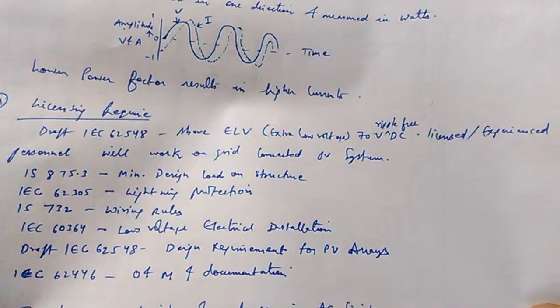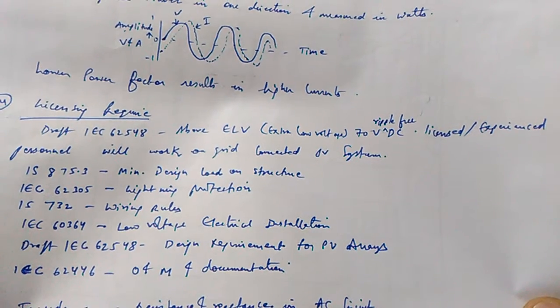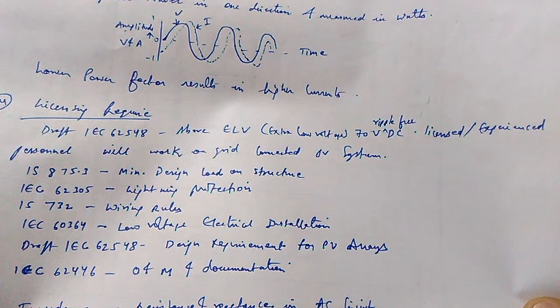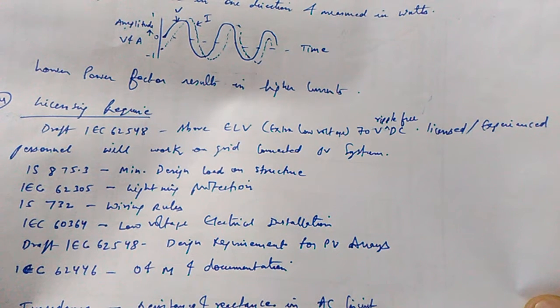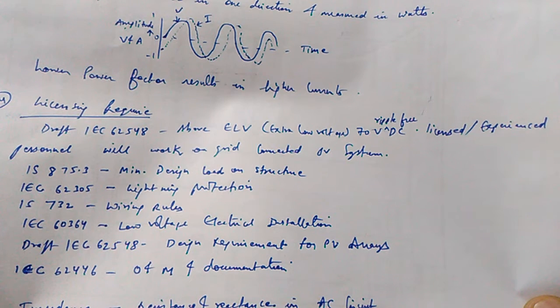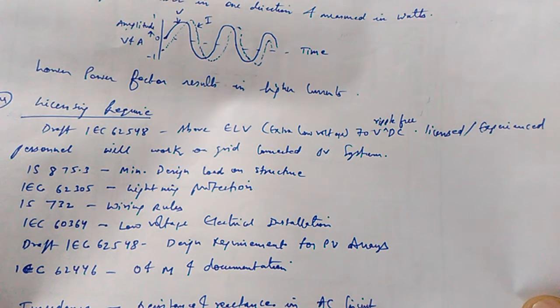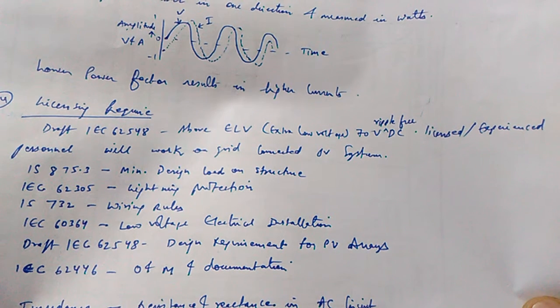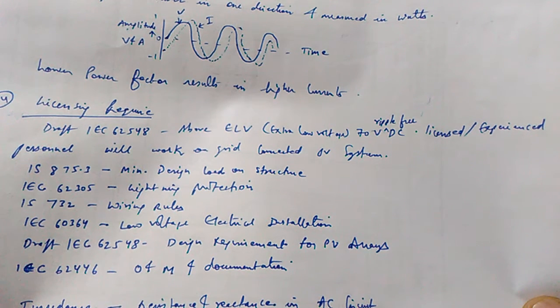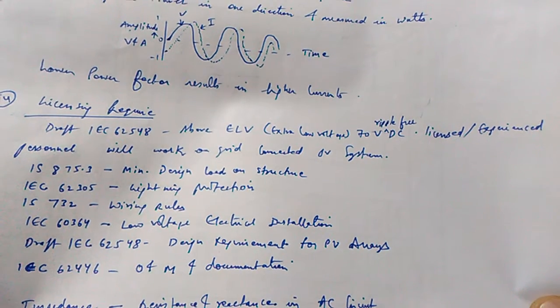Next one is licensing requirement. Draft IEC 62548 above ELV. ELV means extra low voltage, 70 volts ripple free DC. A licensed and experienced person will work on grid connected PV systems. IS 875.3 minimum design load on structure. IEC 62305 lightning protection. IS 732 wiring rules. IEC 60364 low voltage electrical installation. Draft IEC 62548 design requirement for PV system, PV arrays. IEC 62446 O&M and documentation.